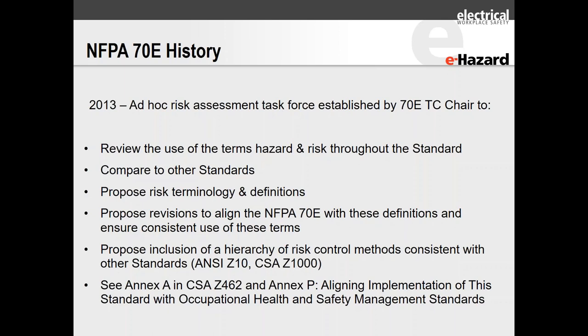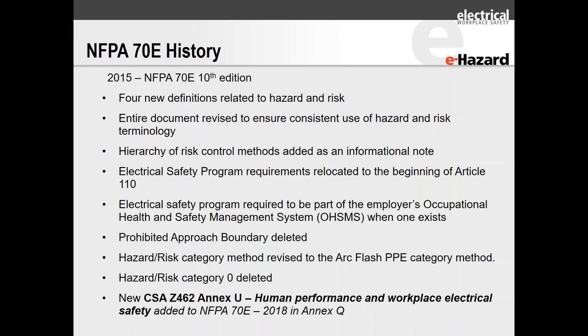This isn't so much about electrical safety — it's about electrical safety management. How do you manage electrical safety in your place of business? In NFPA 70E 2015, the 10th edition, four new definitions related to hazard and risk were added. The entire document was revised to ensure consistent use of hazard and risk terminology. The hierarchy of risk control methods was added as an informational note. In 70E 2018, it went from an informational note right to the cover — the triangle on the cover is the hierarchy of risk control methods.